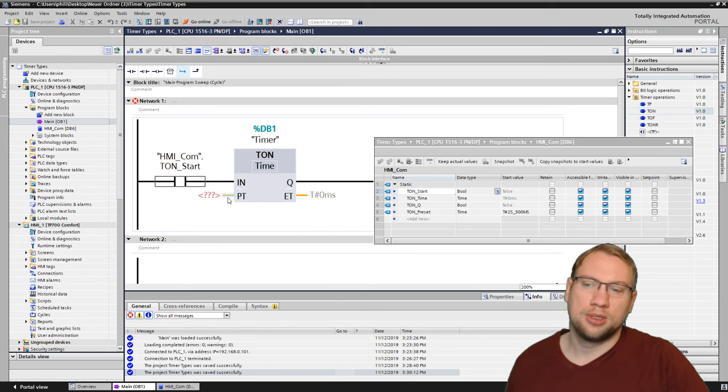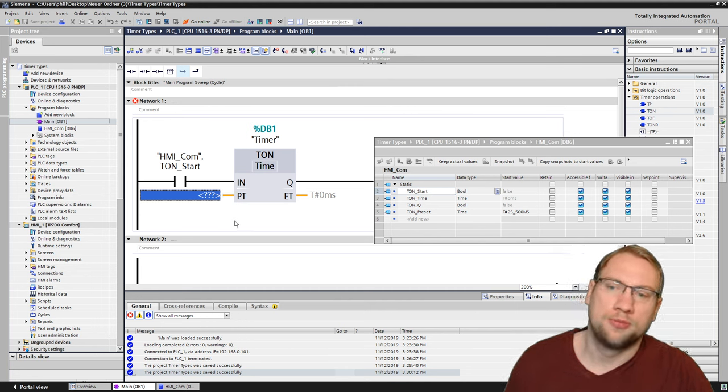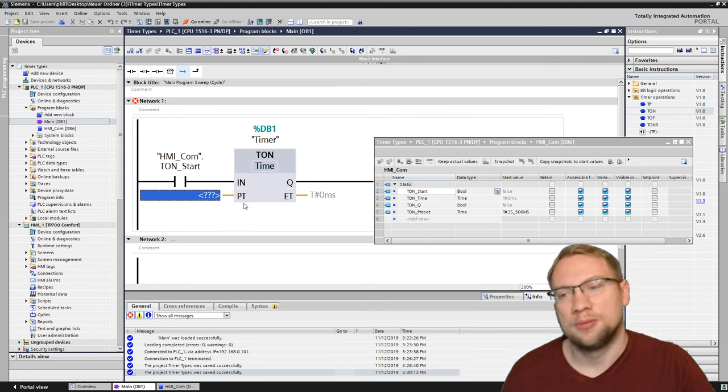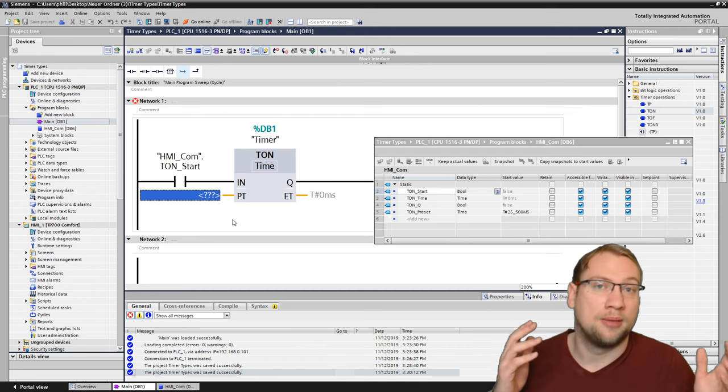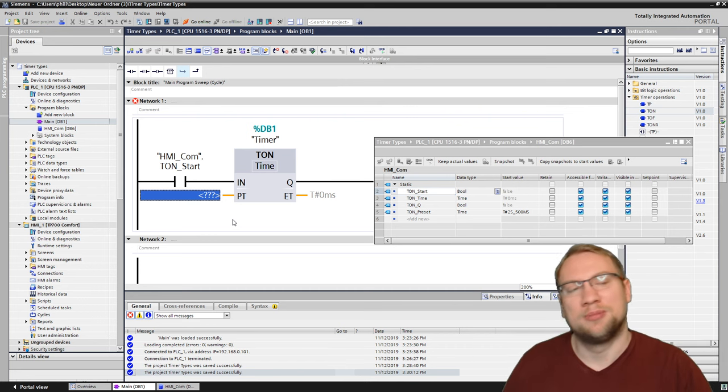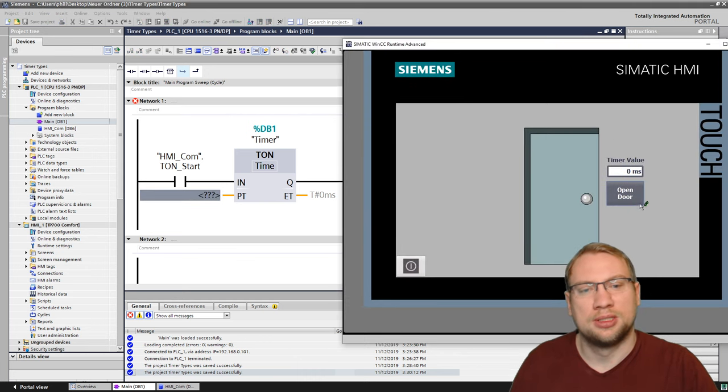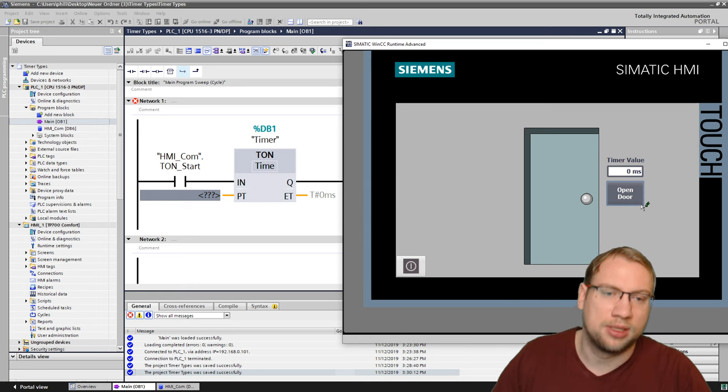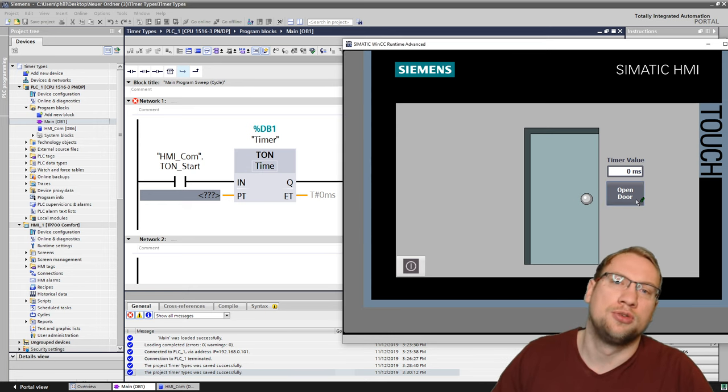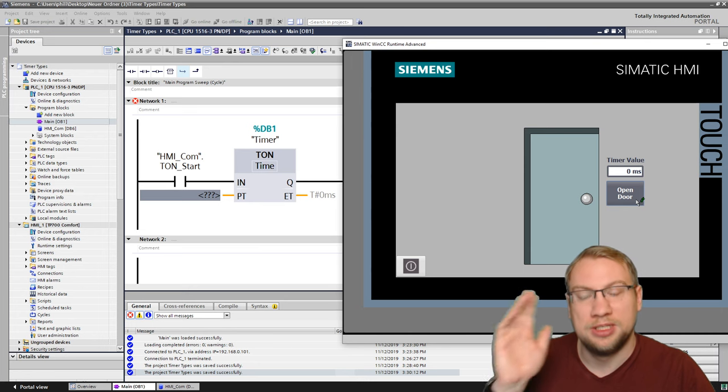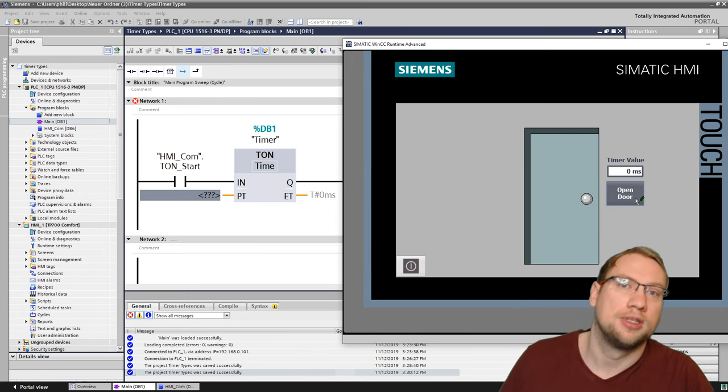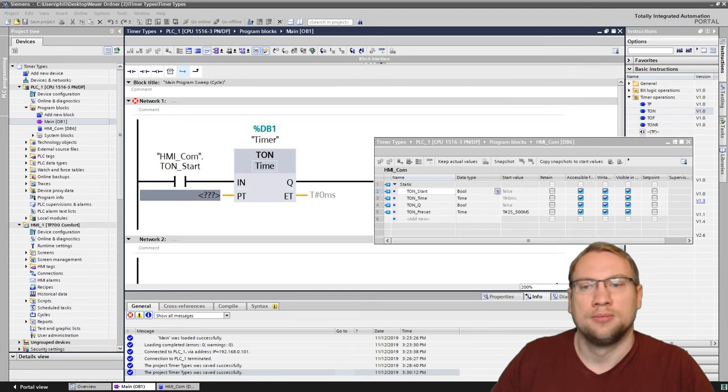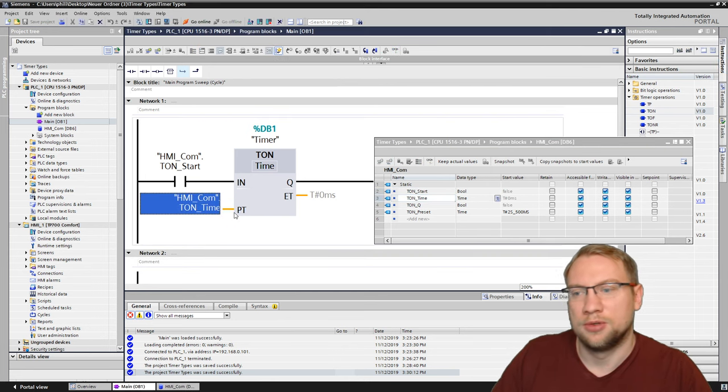The next thing we want is this PT. This is the so-called preset time. The preset time is the time that the timer should be timing. In our case, I want to press this button for 2.5 seconds. And after 2.5 seconds, the door should open. So this PT, the preset time, has to be 2.5 seconds. So this is my TON time. That's how I called it. I'll put it in here.